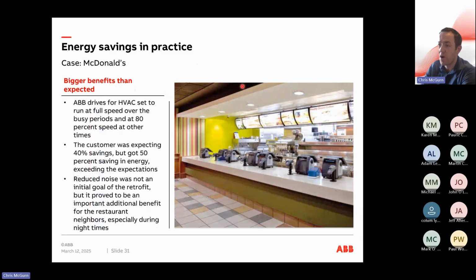So here are some energy savings in practice, some case studies performed by ABB across the world that showed improvements. This is an HVAC system for McDonald's. The HVAC was set to run at full speed for busy periods and 80% speed at other times. The customer was expecting 40% savings by switching to a VSD system, but got 50% in reality, so it exceeded their expectations. Additionally, they had reduced noise, which wasn't part of their plan, but was an additional benefit and helped with customers on site and for their neighbours in the vicinity.